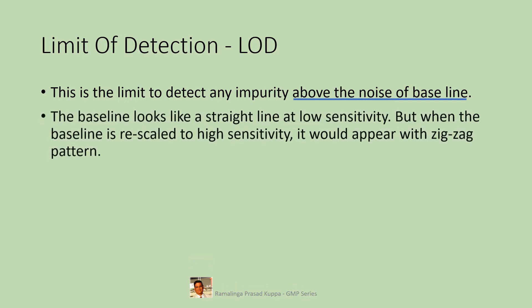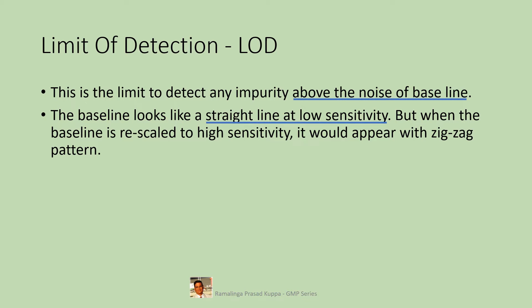Limit of detection, LOD, is the limit to detect any impurity above the noise of the baseline. When there is an impurity or any organic entity going through the detector cell in HPLC or GC, you get a signal. When there is no such impurity going through the detector, there is no signal. Whatever small disturbances get recorded is called noise. So when there is no signal, the detector disturbances will be only noise.